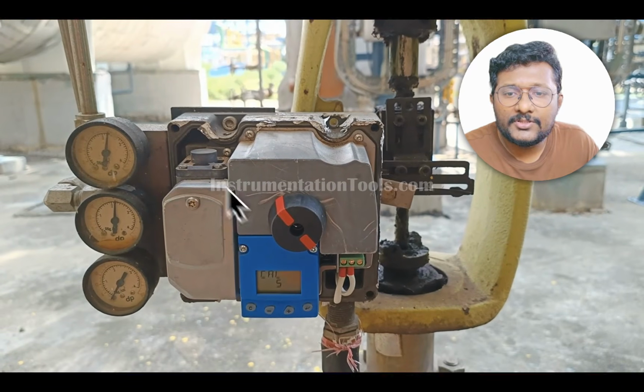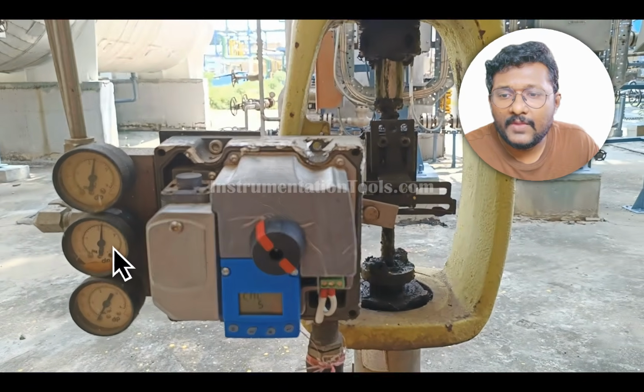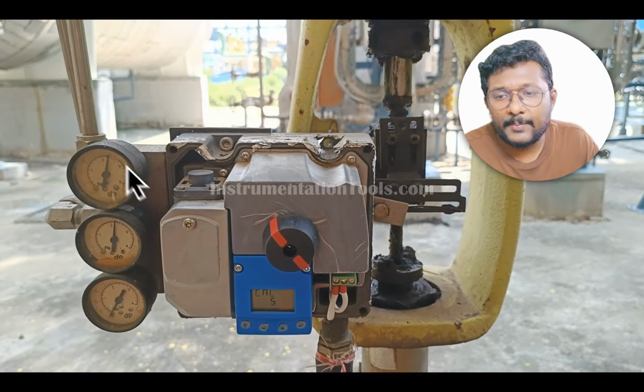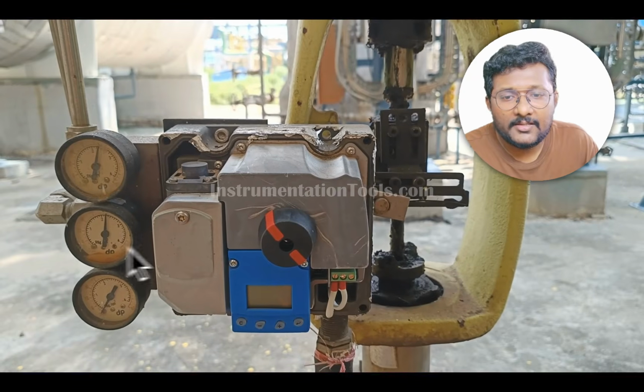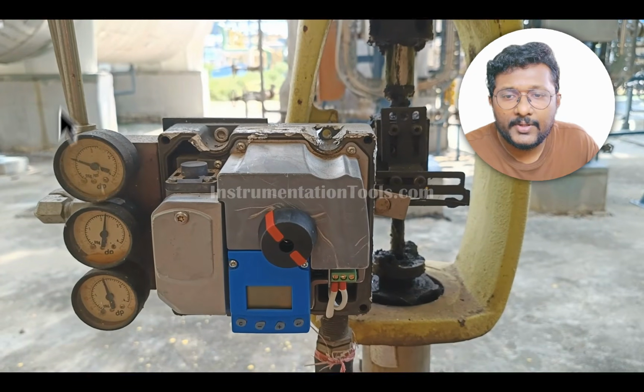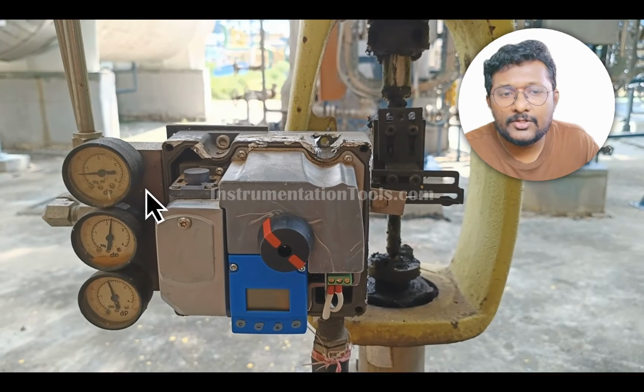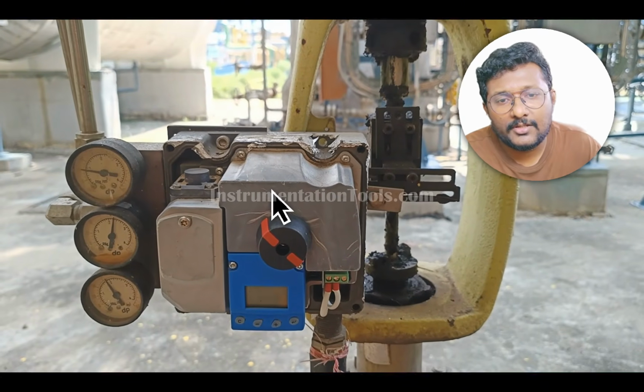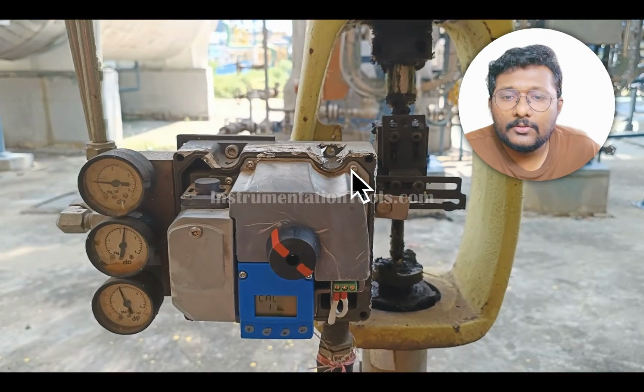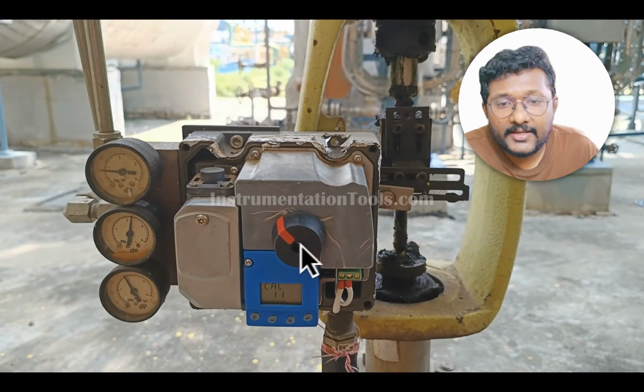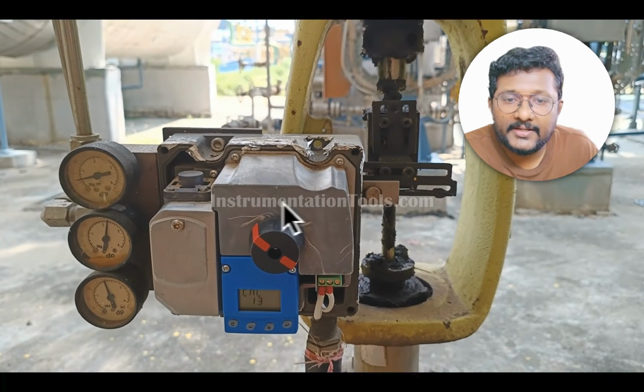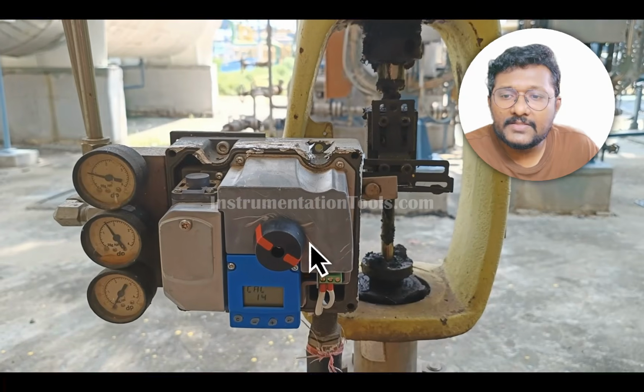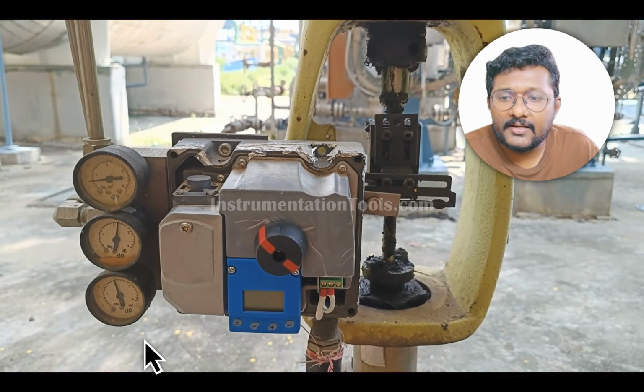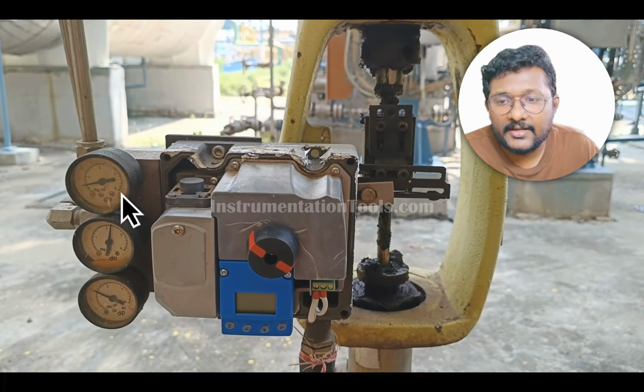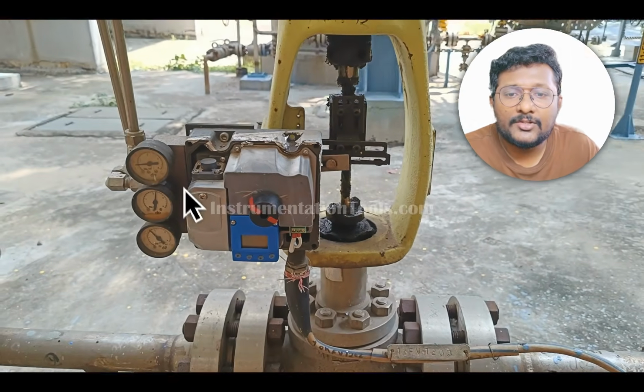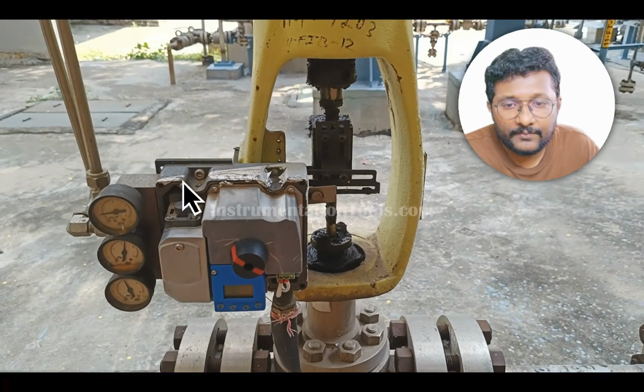Remember, the valve positioner receives the instrument air supply. So you can see the gauges here, the pressure gauges. You can see the inlet instrument air, outlet instrument air, right? The outlet means instrument air going from the valve positioner to the actuator. So the valve positioner regulates or controls the instrument air supply, right? That is why you can see the pressure gauges here. They are not constant. Their pointer is moving. That means the instrument air supply is regulating, right?